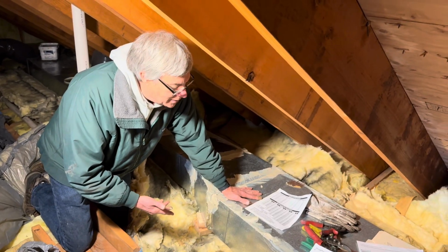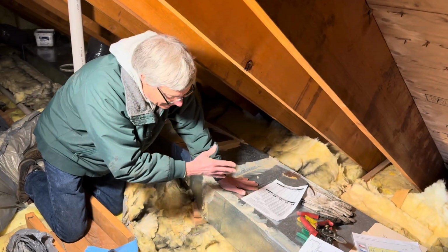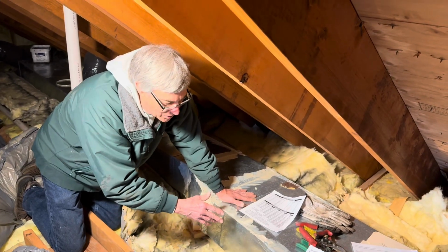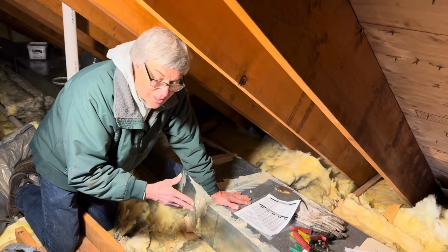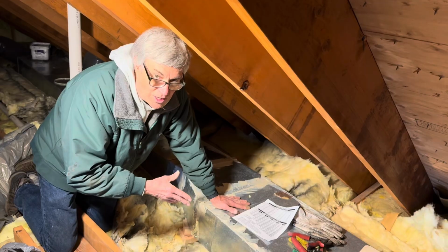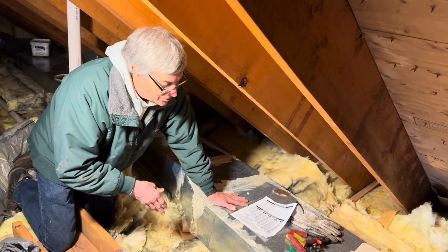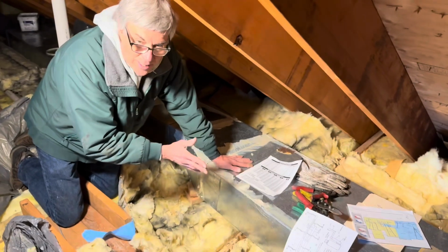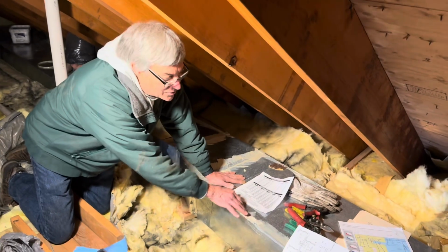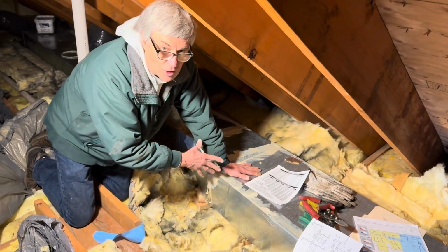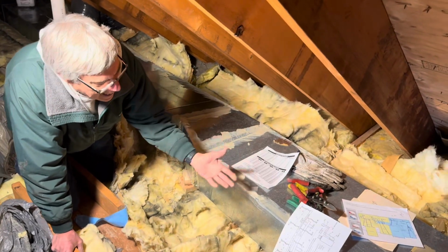And then when we're all done, we're going to take all this stuff that is now sealed very well, and we're going to wrap it better with insulation and put it all back, because then we're going to preserve more heat. Because in the summertime this attic is 130 degrees, and in the wintertime this attic is 30 degrees. So by having a greater barrier of separation between the attic, through the insulation, and the duct system, we also don't have a lot of loss of heat. So we're going to add that too.